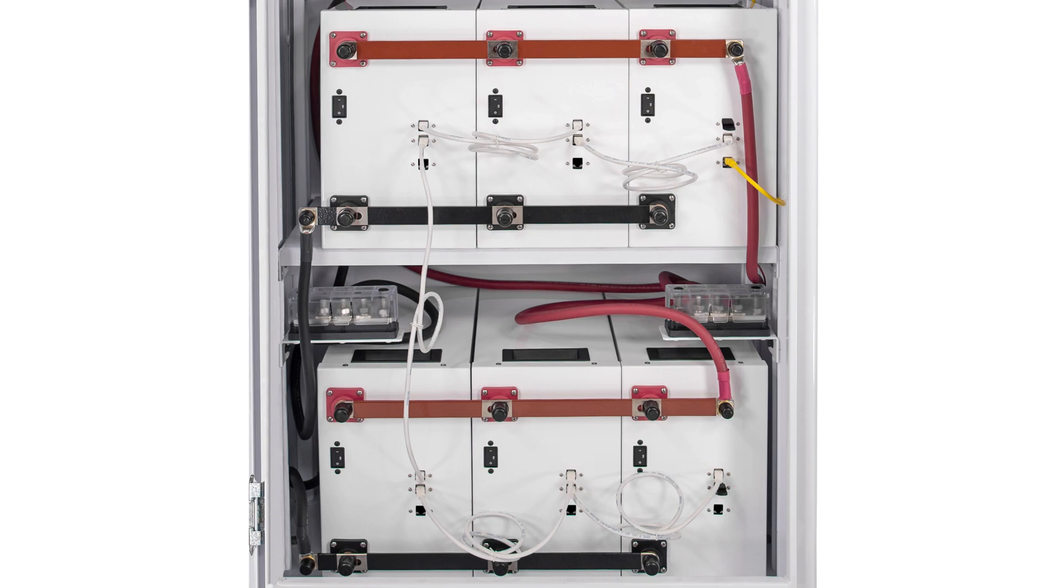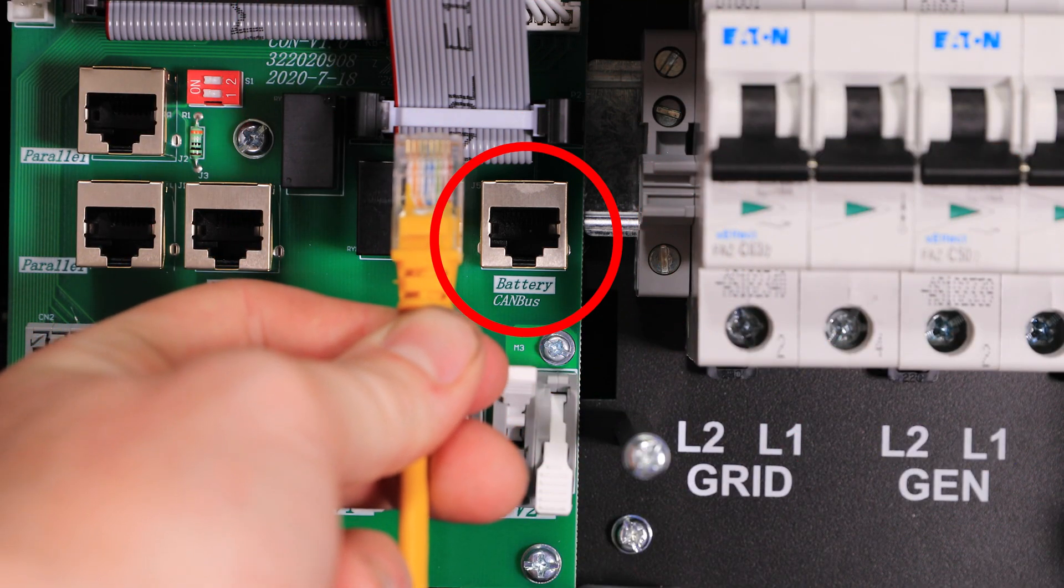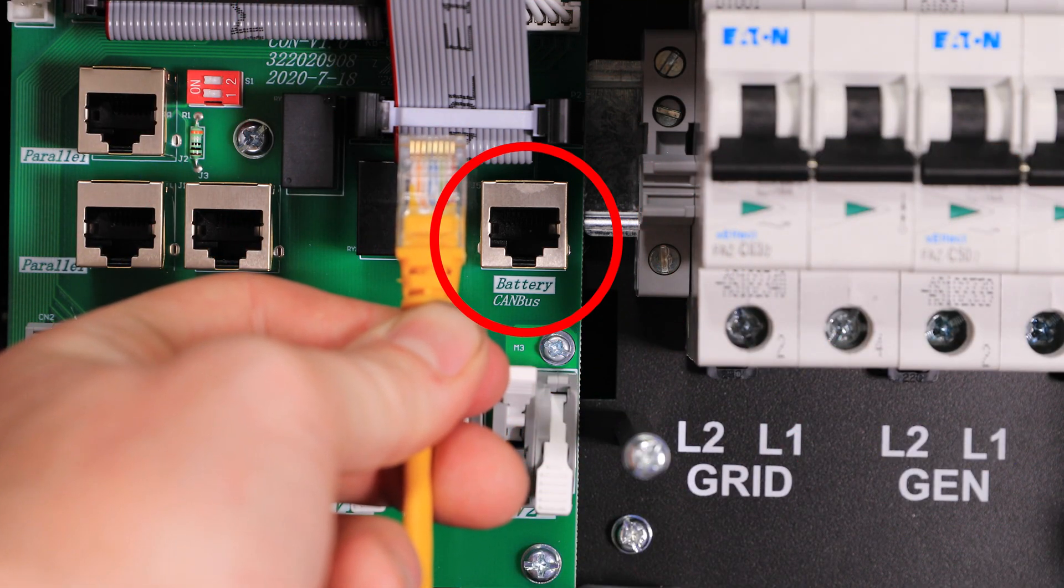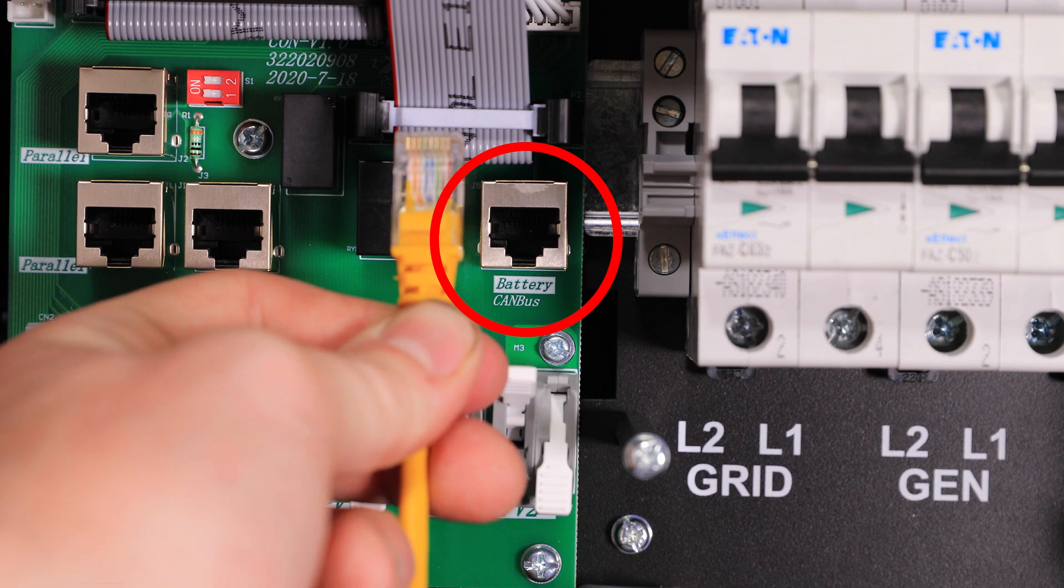Last, use a Cat5 cable not longer than 40 feet to connect only one battery in the bank to the inverter. This cable will connect to the port labeled device on the battery and the port labeled Battery CANbus on the inverter. This cable is not included with individual batteries but can be easily sourced.